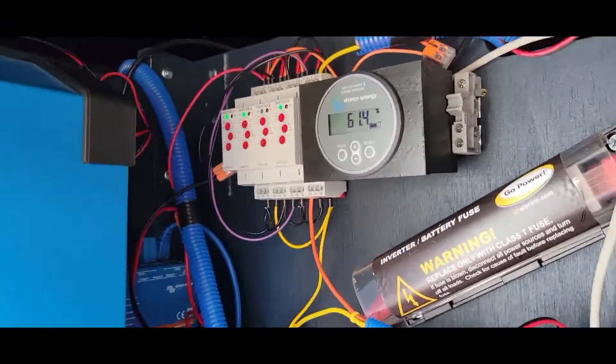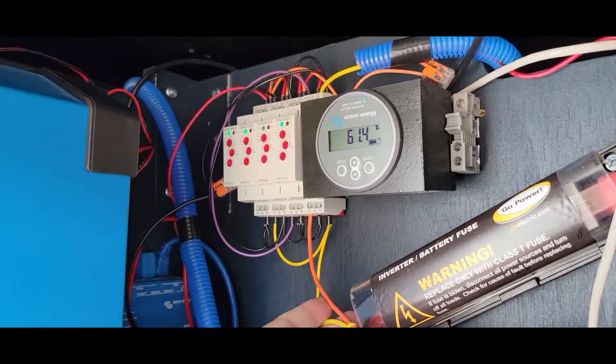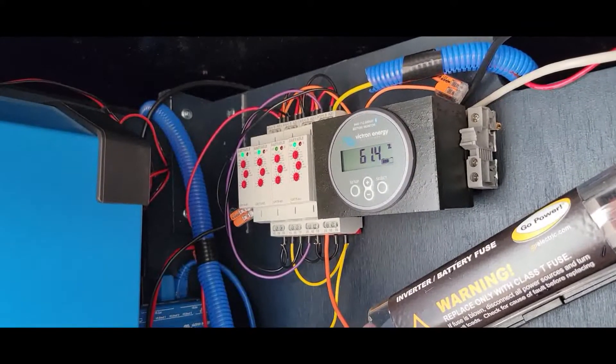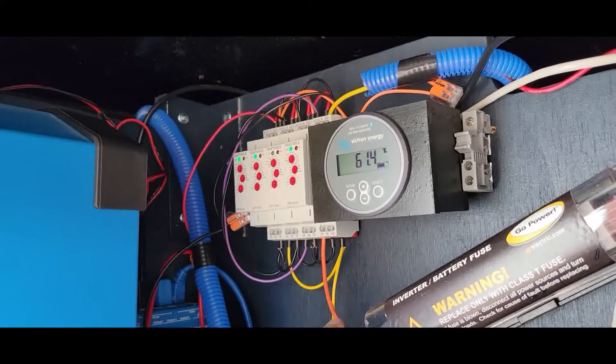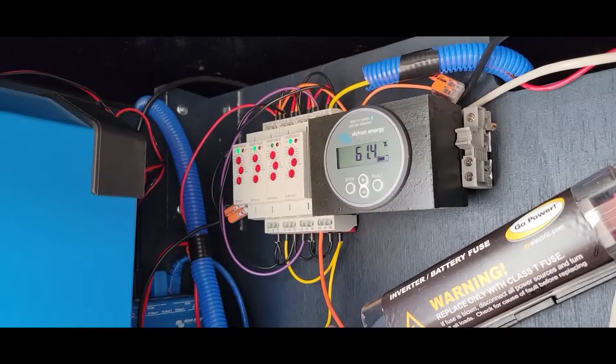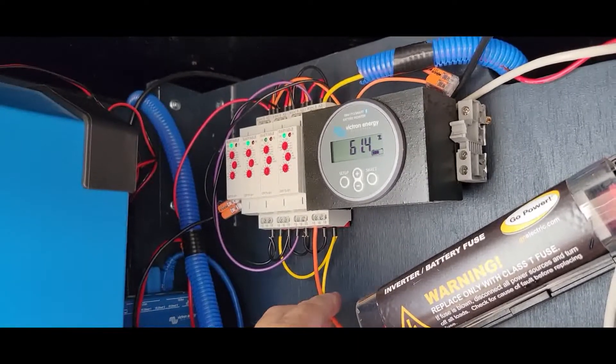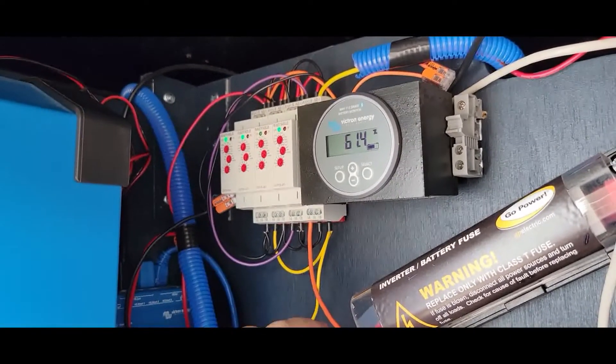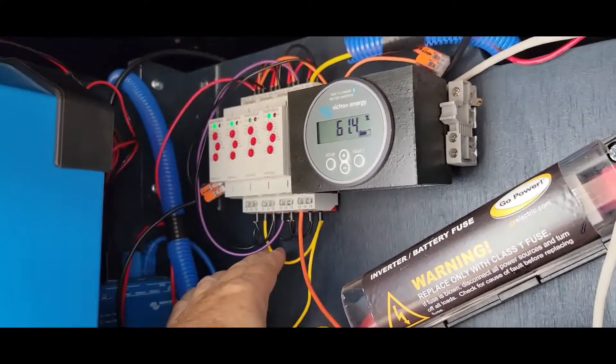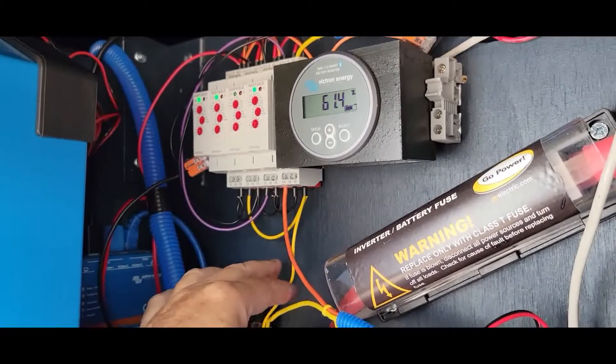The wiring here, these two, the orange and yellow, is the signal going out to my G7 panel. So I spliced in my G7 panel, which is where the generator wires are going to. I have the start as orange and the yellow as a stop. As you can see, the first relay is tied into the fourth relay as a stop.